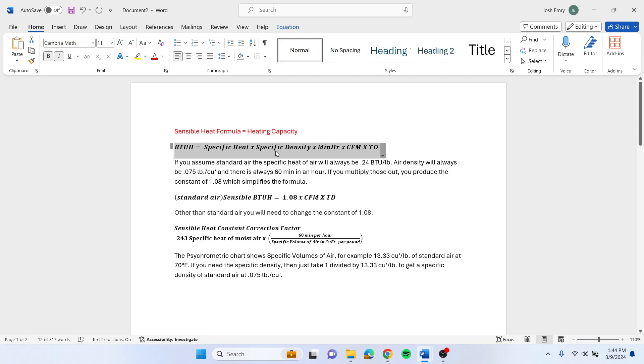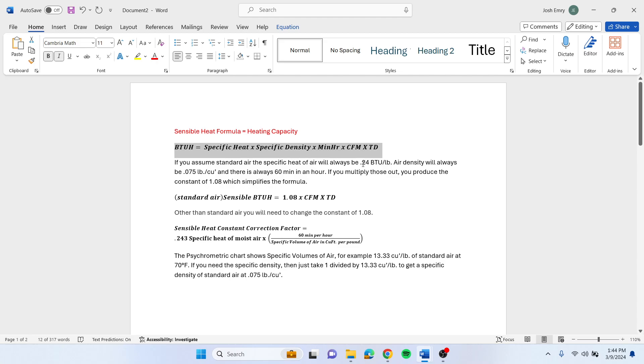What they end up doing is they figure standard air, so you're not doing real high temperatures or real low temperatures. So you're always at 0.075 cubic feet per pound, and there's 60 minutes in an hour always, and you're always 0.24 BTUs per pound. They take all that, times it out, and once they get that multiplied out, you end up with this 1.08 constant. That's where this formula comes from.